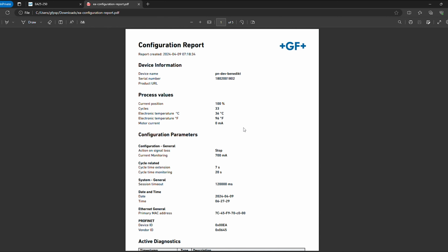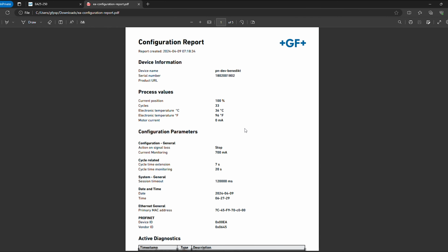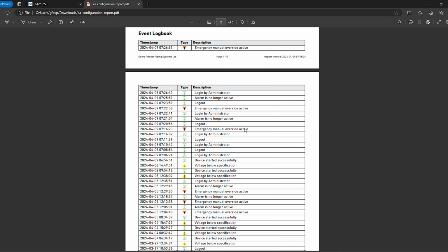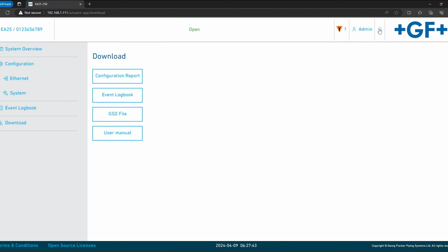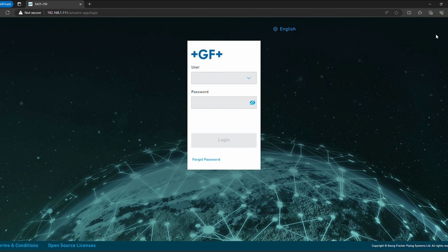The electric actuator provides static downloads, such as the user manual and the device driver for the PLC integration, but also generated reports with all parameter values, which can be used as documentation after commissioning. The event logbook is also part of this report. The embedded web server creates added value and is security certified according to IEC 62443.